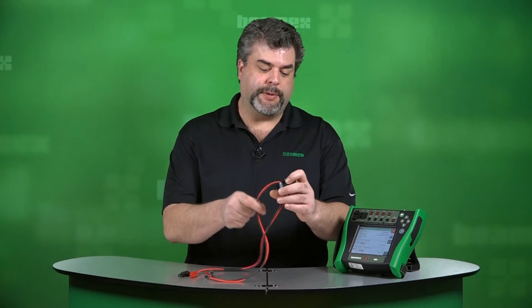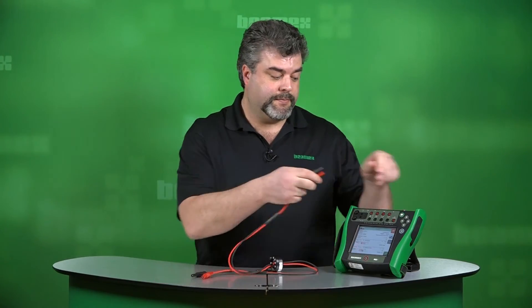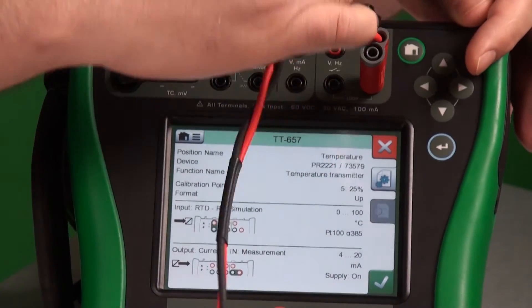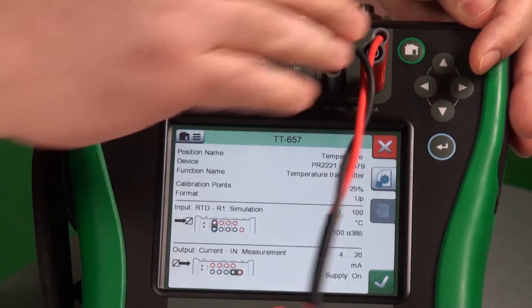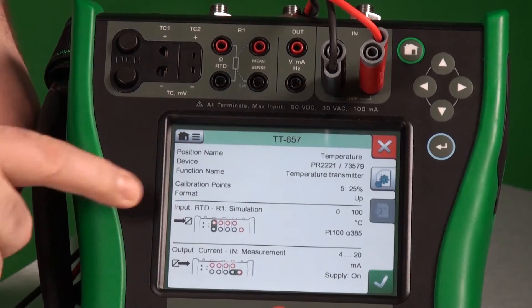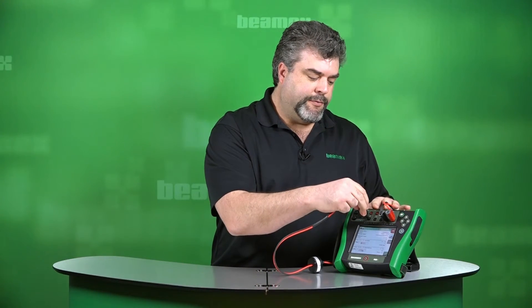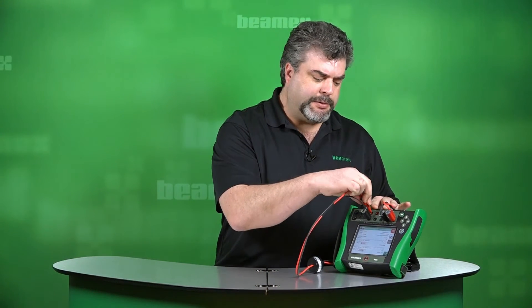It tells me where to hook up. I'll take my temperature transmitter — I'm holding on to the output section, and the output here is on the bottom, so that tells me to hook up right here. This is where I'll measure current and where it will also provide loop power. Now if I did have a three or four wire RTD setup, I would simply stack the leads — if I had two black leads, I'd stack those two, and two red, you stack those.